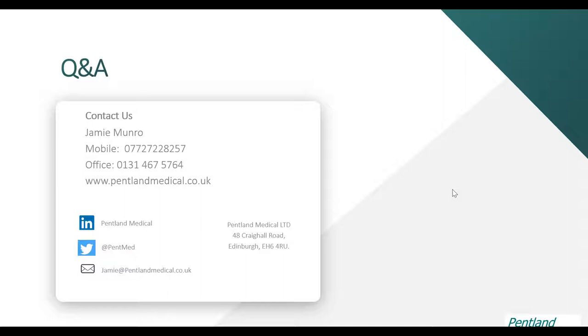Now, just like I said, it's a drip counter, so you cannot use it for life-saving medications. But I'd like to highlight that the drip flow sets, the dial flow sets, are even more inaccurate, and many trusts have actually banned them. Also, I'm not sure if it came up in the presentations, but the Monidrop is used with gravity sets that are 20 drops per mil. So you cannot use it with a buretrol set or with sets that are 50 drops per mil. Luckily, though, most gravity sets have been calibrated to 20 drops per mil. Thank you.